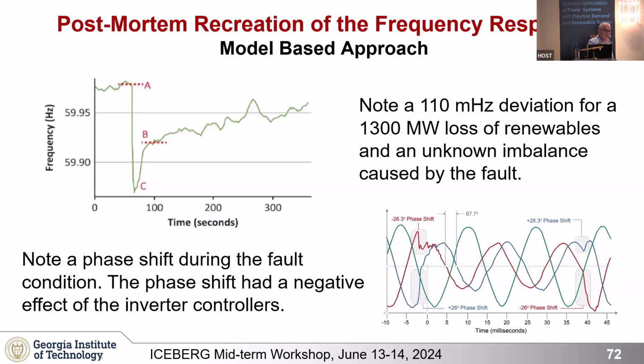In addition, the experimental approach is difficult from another point of view. Here is the recreation of an event that happened in California, around 2016, where because of these transients, about 1,300 megawatts of PV facility dropped out. The reason was a fault on a 500 kV line, which cleared within about 2.5 cycles, but during the fault it generated a phase shift, and when the fault cleared, the phase shift went back again.